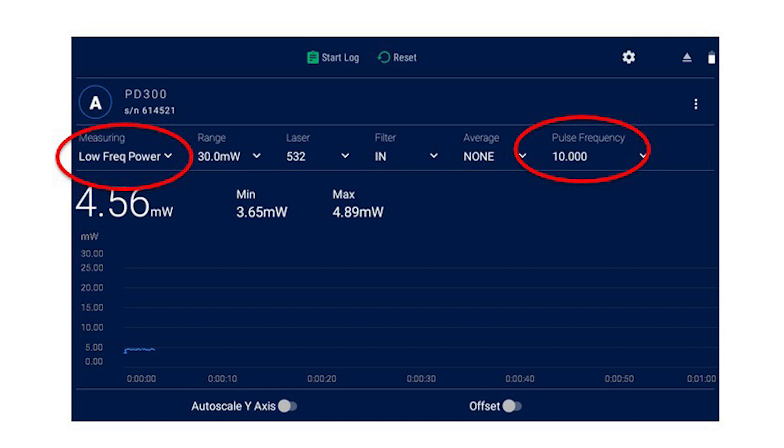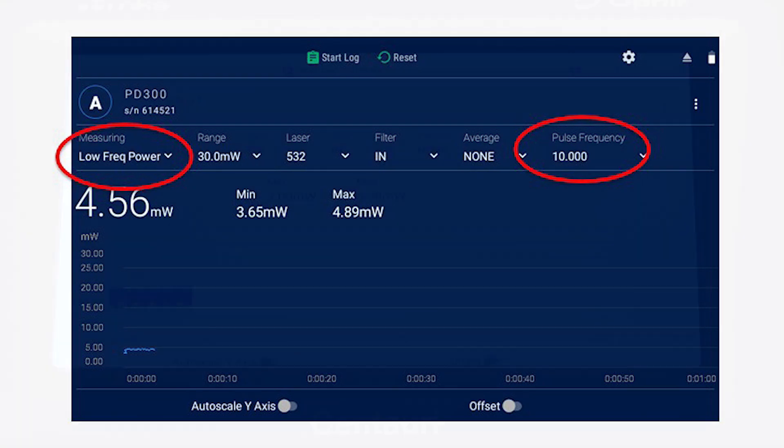The sampling rate is adjusted to match the actual pulse frequency, which the user is prompted to enter. No more beat frequency. The gain is lowered, and the resolution is increased, so that we get accurate measurements of the low average power without being thrown off by saturation caused by the high peak power.